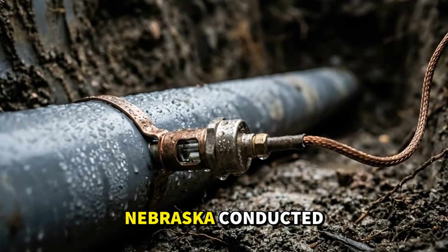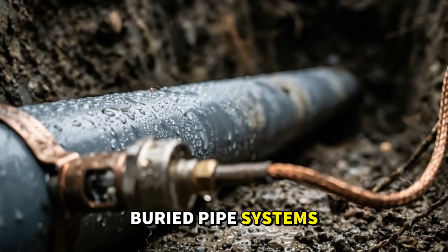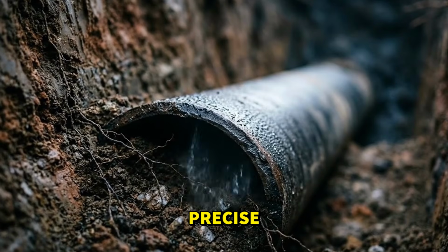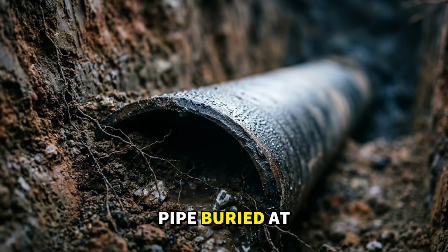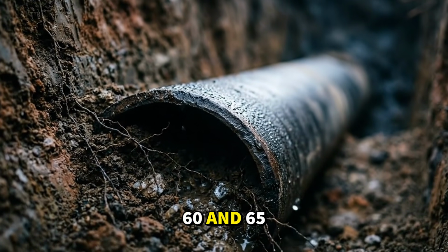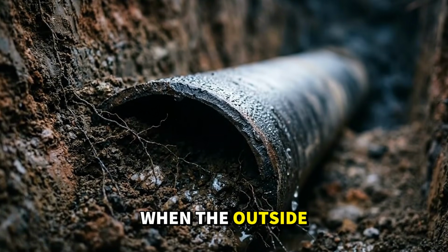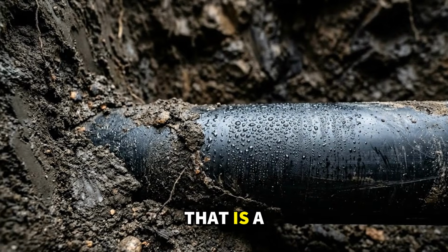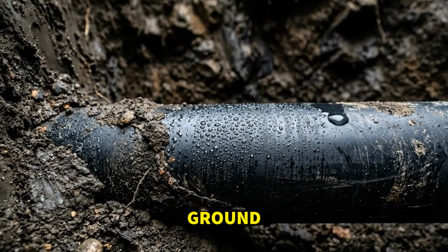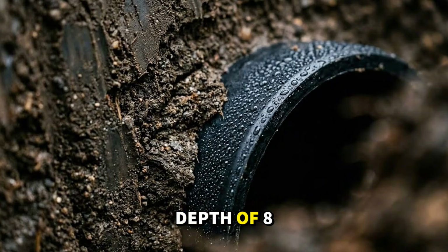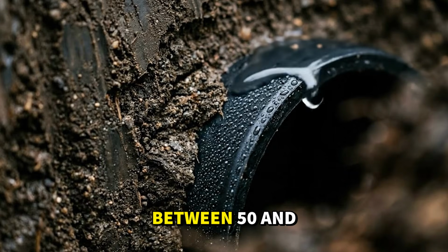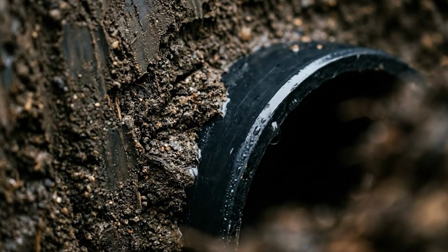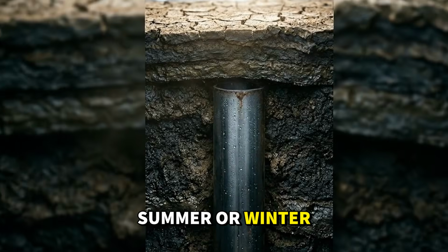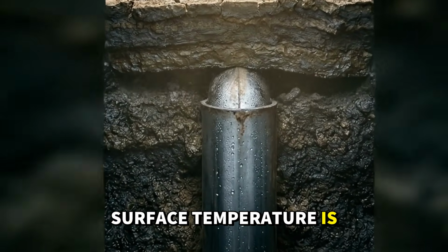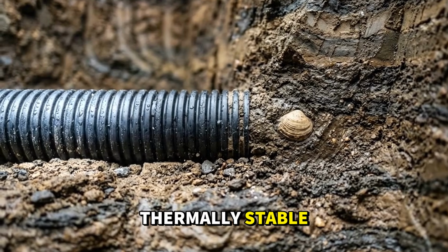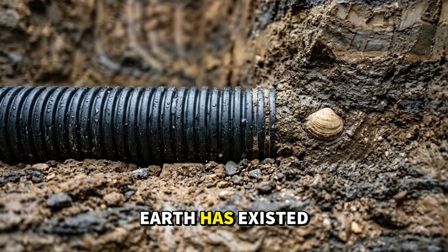The University of Nebraska conducted field measurements on buried pipe systems in the 1980s. Their finding was precise. 200 feet of 6-inch diameter pipe, buried at optimal depth, delivers air between 60 and 65 degrees Fahrenheit, when the outside ambient temperature is in the mid-90s. That is a 30-degree temperature drop from a pipe in the ground. The mechanism is simple. At a depth of 8 to 10 feet, soil temperature stabilizes between 50 and 55 degrees Fahrenheit, year-round. Summer or winter. It does not matter what the surface temperature is. The Earth at that depth is thermally stable. It has been stable for as long as the Earth has existed.